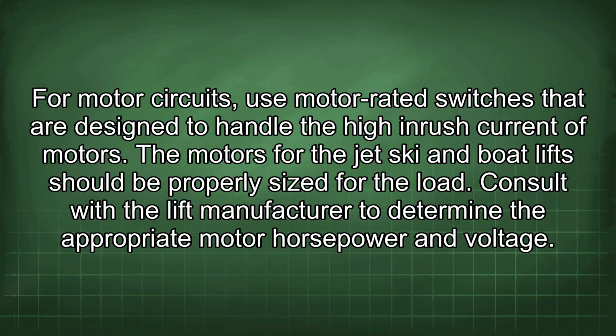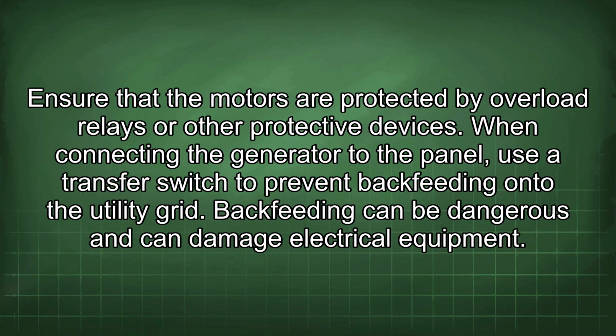The motors for the jet ski and boat lift should be properly sized for the load. Consult with the lift manufacturer to determine the appropriate motor horsepower and voltage. Ensure that the motors are protected by overload relays or other protective devices. When connecting the generator to the panel, use a transfer switch to prevent backfeeding onto the utility grid. Backfeeding can be dangerous and can damage electrical equipment.